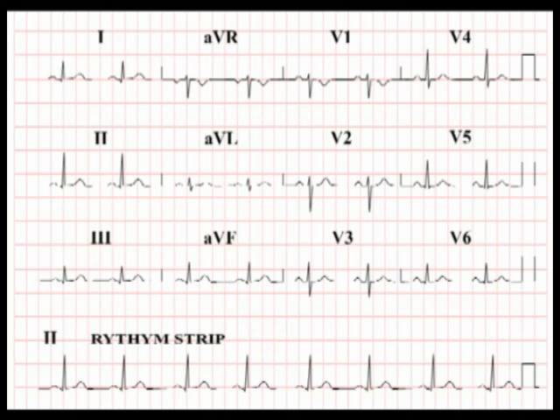ECG recording paper is divided into large squares 5 mm wide, and these large squares are in turn further subdivided into small squares each of 1 mm in width. We can consider that in all ECG machines the recording needles run at a constant speed over the ECG paper of 25 mm per second. This means that distance on the ECG paper equates to time.